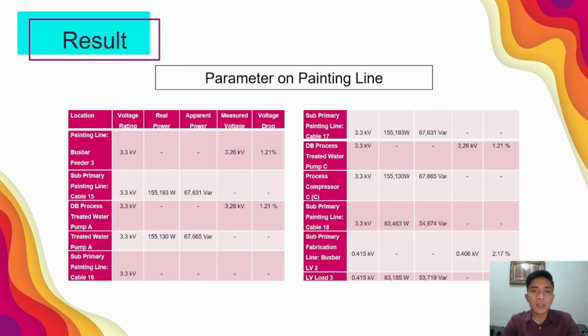Okay, lastly, the parameters on the painting line, which is the last line in this car manufacturing company. So the voltage rating for all loads is 3.3 kV except at the SPDB busbar LV2 and LV load 3 network, which is rated at 0.415 kV.